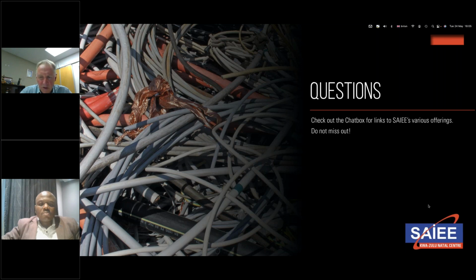So you can have vibration-induced fatigue and breakages even at low levels of vibration. So one should be careful with the use of aluminium where there's known vibration present. Rather eliminate the source or use copper.